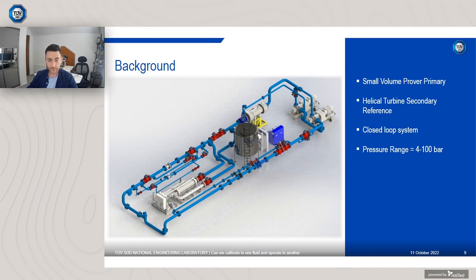It has a pressure range from 4 to 100 bar. So this is a liquid flow facility that can go up to 100 bar. It's one of the only ones in the world that can operate at such elevated pressures. And we operate from 20 degrees to 80 degrees Celsius. So again, extremely high temperatures, high pressures. The temperature can be kept stable for the whole calibration within plus or minus 0.5 degrees C, and pressure within plus or minus 0.25 bar for the entire calibration. So extremely stable temperature and pressure.